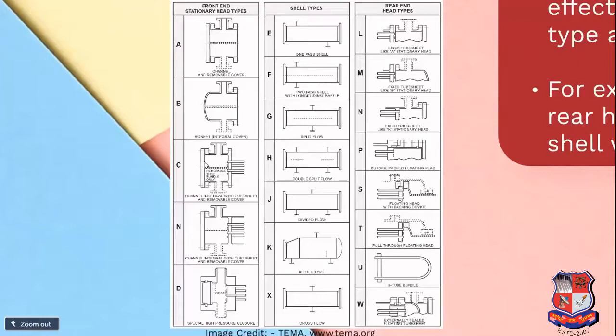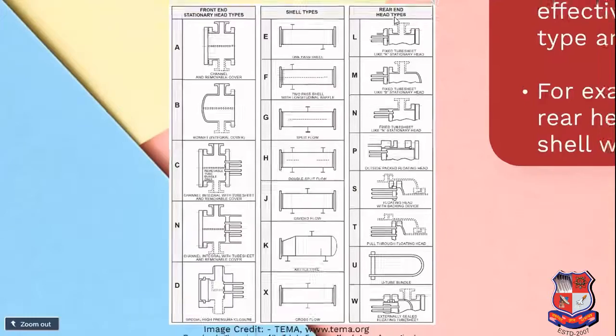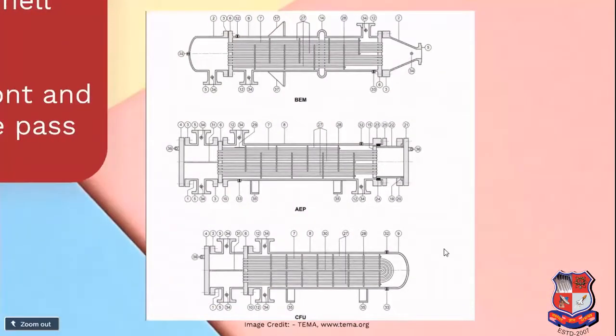Then the next letter was F. F is two shell pass with longitudinal baffle. Again here you can see the longitudinal baffle which splits the shell passes in two. Last one was U, where U stands for U type of bundle or tube bundle, where due to this the head changes accordingly. Here you can see the head is either a torispherical or elliptical head. So this helps again in expansion of a tube. I hope you have understood the basic diagram of a heat exchanger and components of it and nomenclature related to it. Thank you.